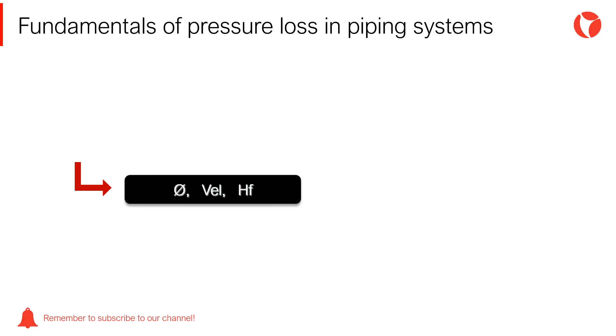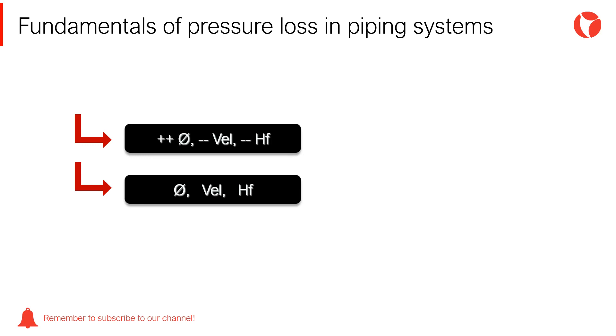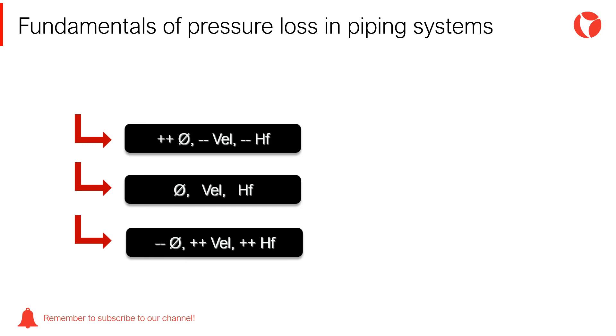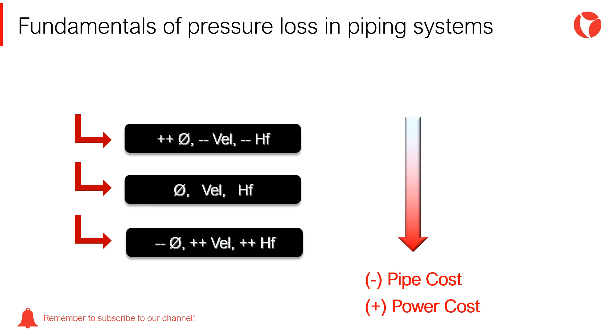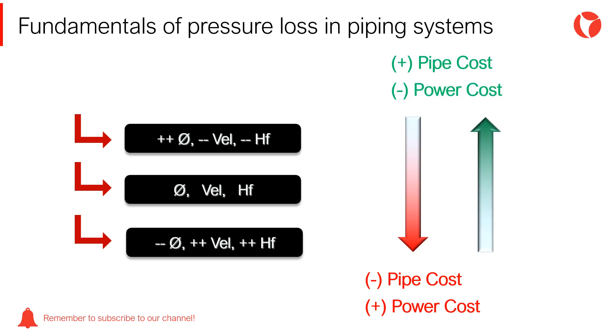For a given diameter, a fixed velocity and pressure loss can be found. If the pressure loss of the system needs to be minimized, the velocity has to decrease, and therefore the diameter of the pipes will increase. If the capital investment of the installation needs to be reduced, the pipe diameter can be reduced, increasing the velocity of the system and thus the pressure loss. Summing up: reducing the diameter means less initial investment and more pressure loss — in other words, more installed power. On the contrary, reducing the pressure loss will require slower velocities and in turn larger diameters.